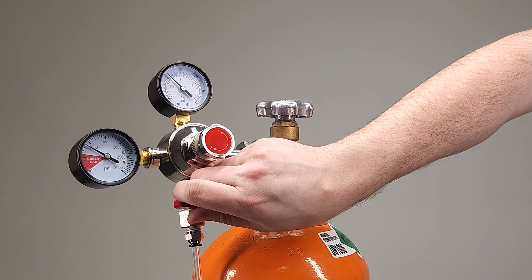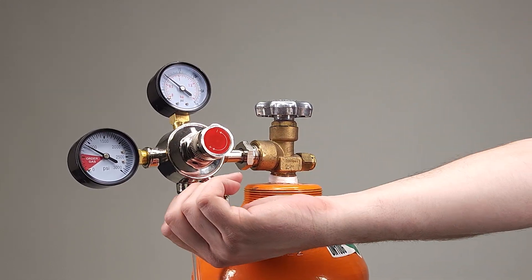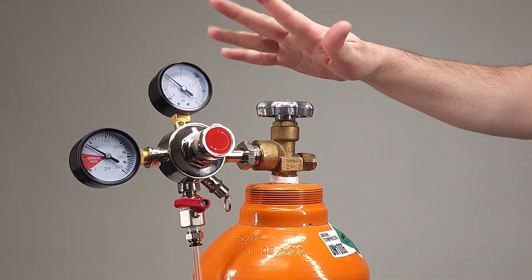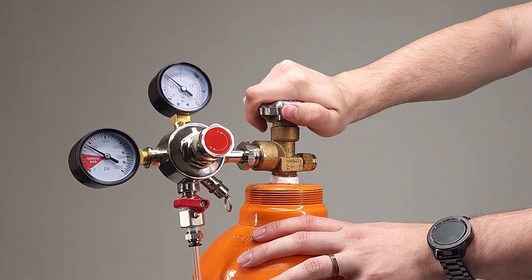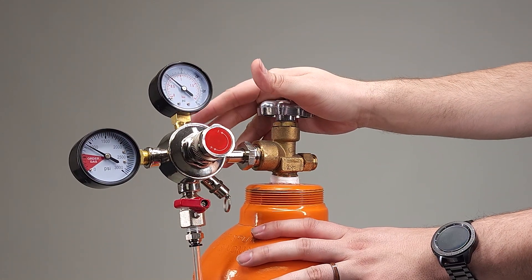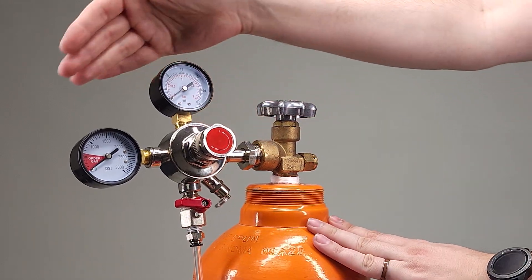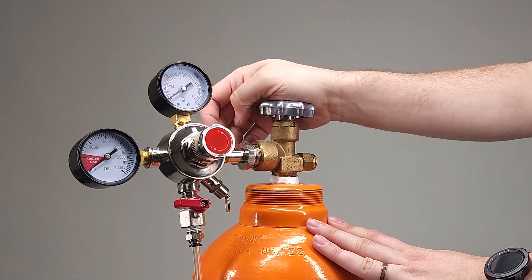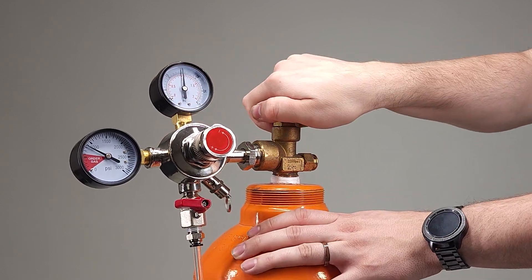Now we can use this valve and flow gas out. At any time we can close that off, but I would personally like to close off the entire tank so there's no leaking whatsoever. It's up to you. If you want to leave the line so that both lines are at zero, or you can just leave them in a pressurized state.